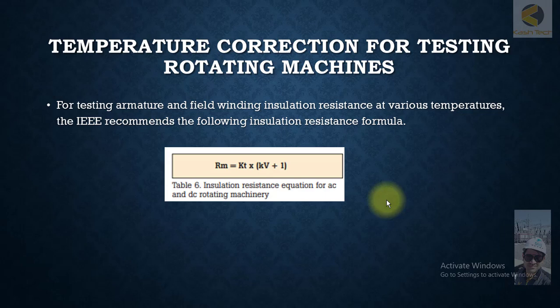Hey friends, we all know that temperature affects the insulation resistance. If the temperature is higher, the insulation resistance will reduce. So while you are doing the maintenance testing, you have to keep the record of all the tests performed over a period of time and check the healthiness of insulation, whether it's improving or decreasing.